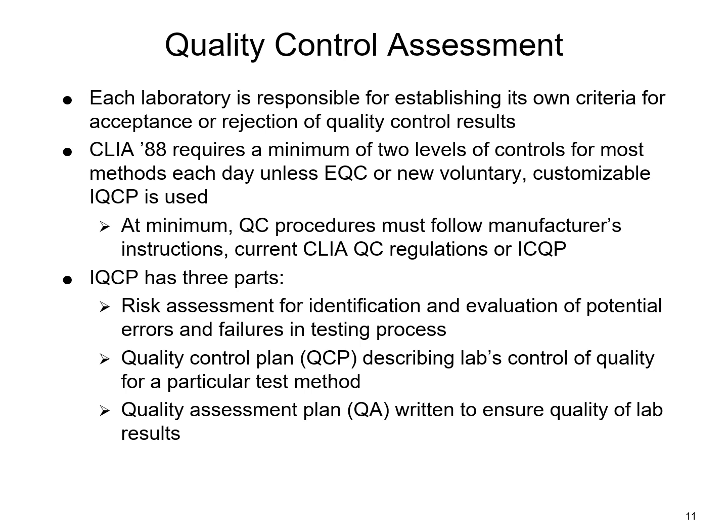Despite the fact CLIA says I'm supposed to run 2 levels of QC daily for a moderate complexity test, which the iStat has been deemed to be, the manufacturer says, hey, that's not necessary. So I still have to establish that I did QC like I was supposed to, that yes, it did follow these rules. I've done the studies, I've put things into place to prevent errors.